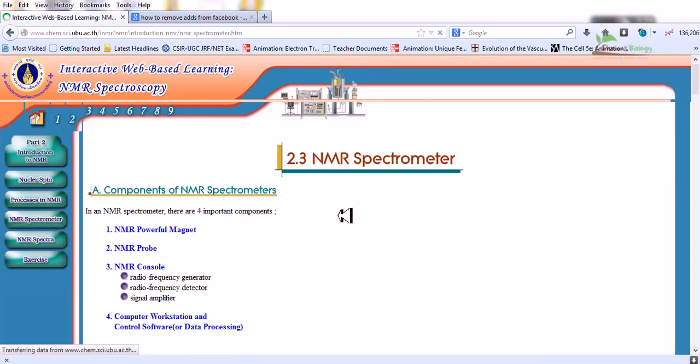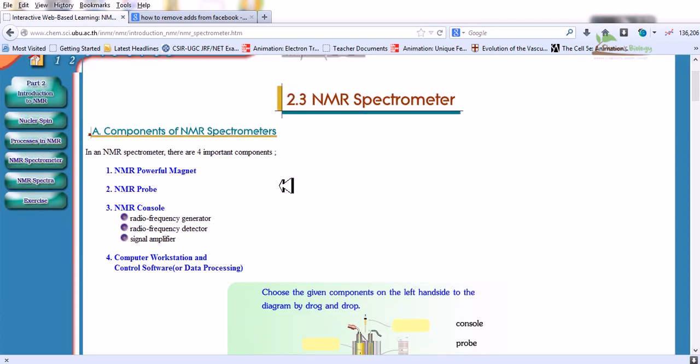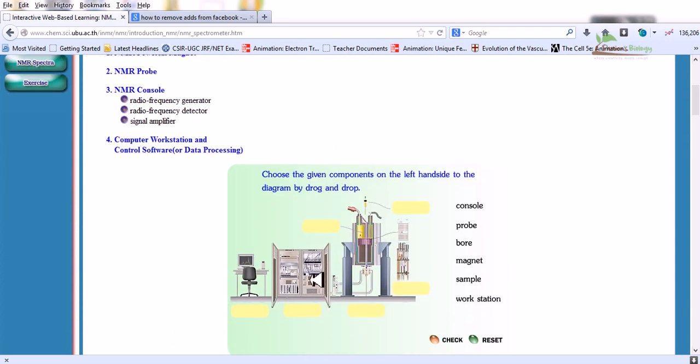Now let us talk about the basic components of an NMR spectrometer. In an NMR spectrometer there are four important components. One is the NMR powerful magnet. Second is the NMR probe. Third is the NMR console, and fourth is the computer workstation or controller software. The NMR console is made up with three different things: the radio frequency generator, the radio frequency detector, and the signal amplifier. We need the complete collaboration of all these units to finally have a fully functional NMR spectrograph.